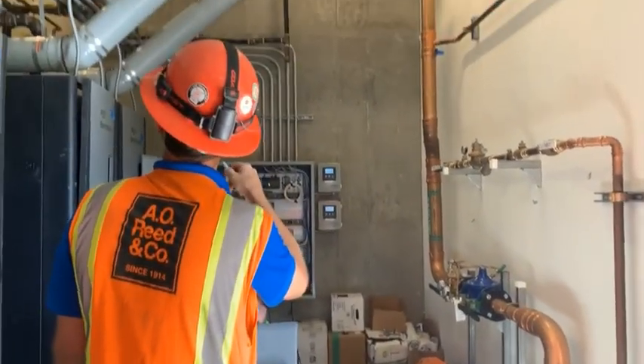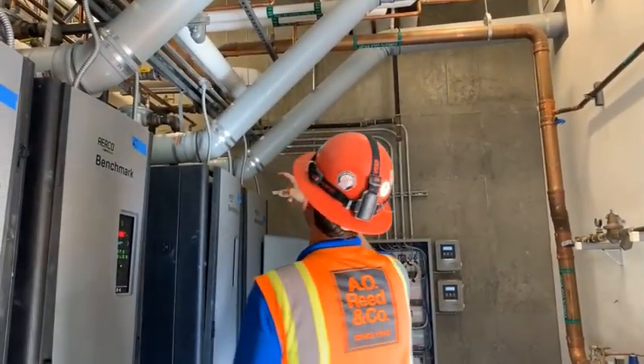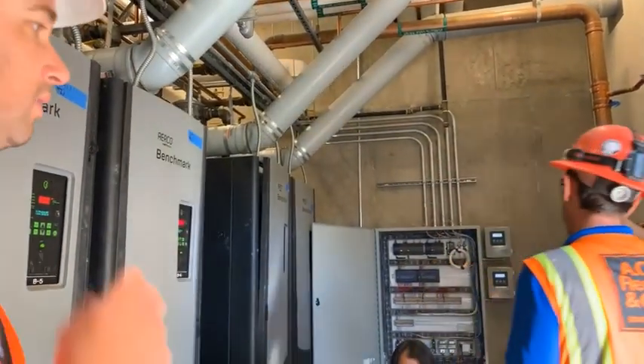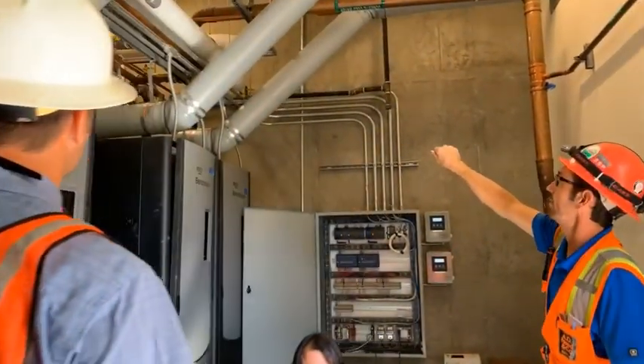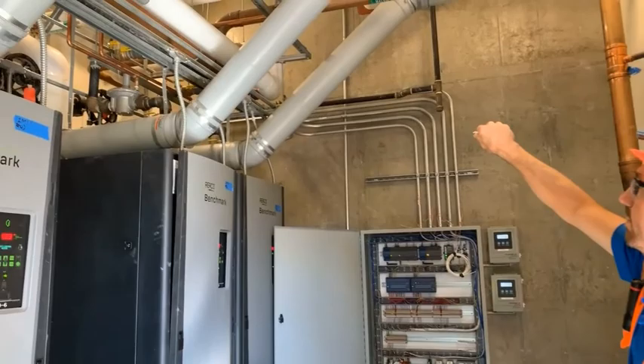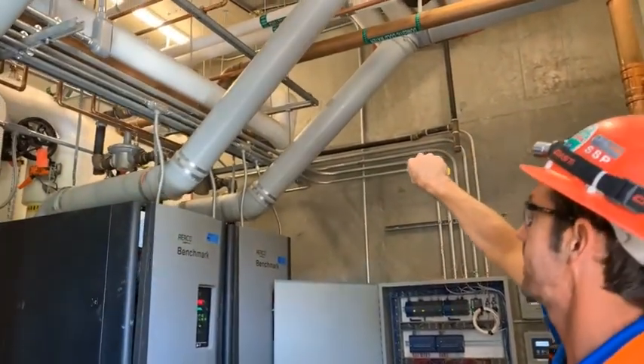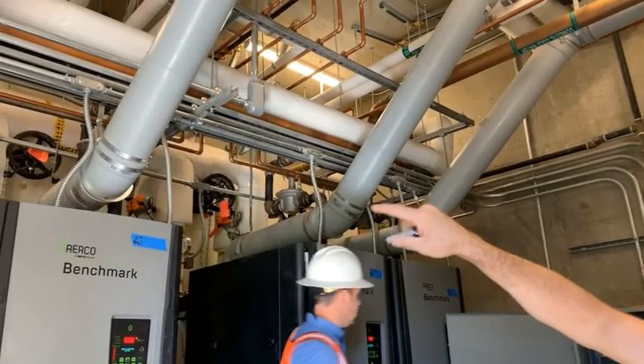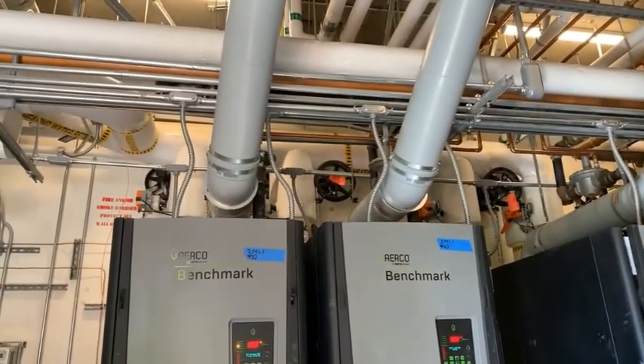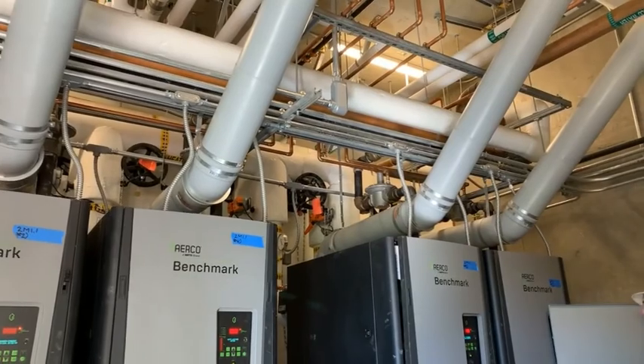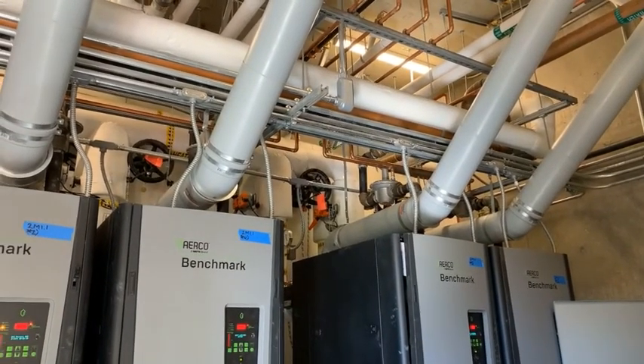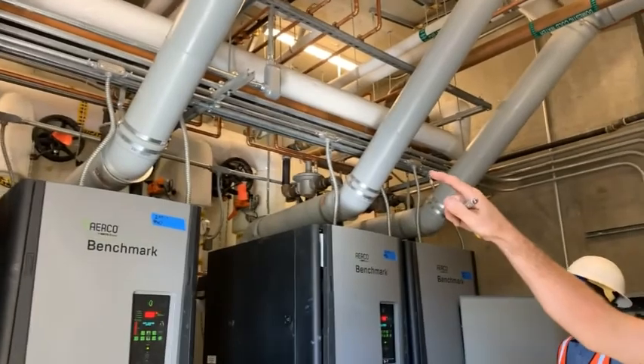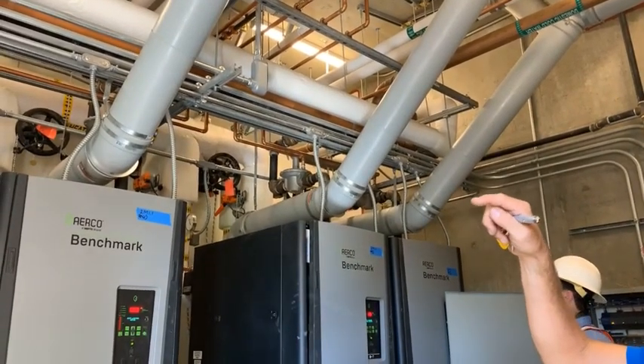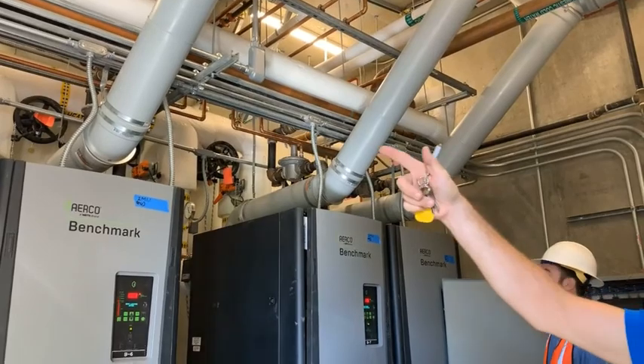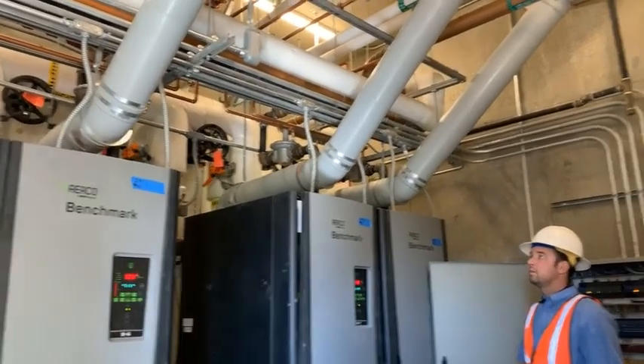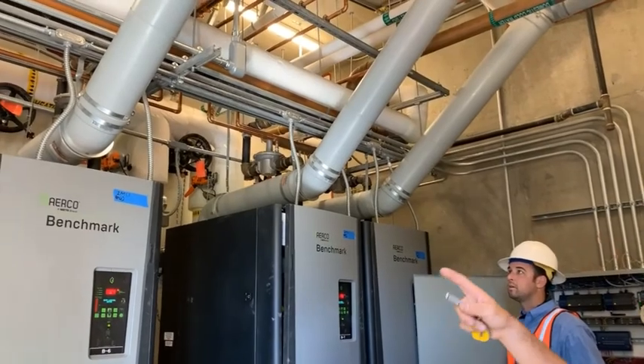Everything else in here is the same as far as the configuration of the pressure reducing valves and the gas. Back in this corner over here, if you can see the laser pointer, we have the main pressure reducing valve for the boilers. Remember, that sets the pressure to all these boilers. The other regs on each boiler, it's not a shut-off valve, it's a flow maintaining valve. It's not a 100% shut-off valve, so you don't adjust the actual static pressure with those regulators. That's only a dynamic set point. That should just be something the boiler guy deals with on your annuals. We shouldn't need to do anything with those.